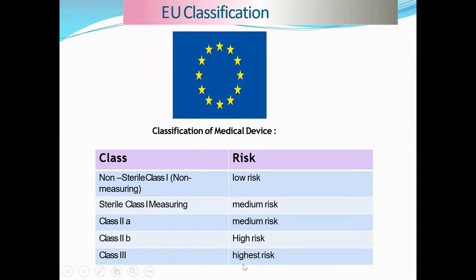So in short, if you compare with the US FDA, there are 3 classes only: low risk, medium, and high. But under low, medium, and high, they have divided into non-sterile and sterile. And here, if you see 2A, 2B: 2A means medium risk, 2B means a little higher risk, but 3 is always highest risk. So please remember, when you are going for the interview, if somebody asks how medical devices are classified in Europe as compared to US, these are the classifications.